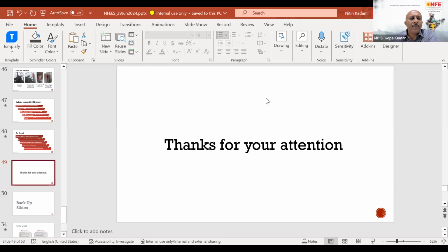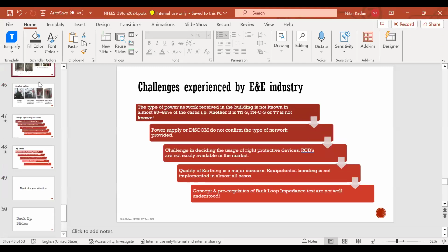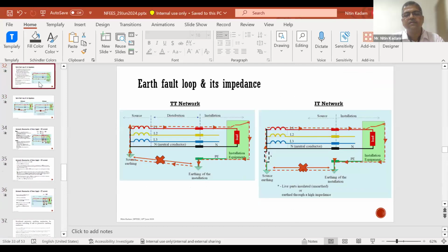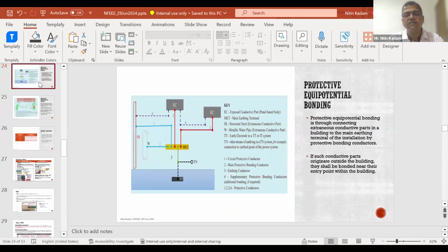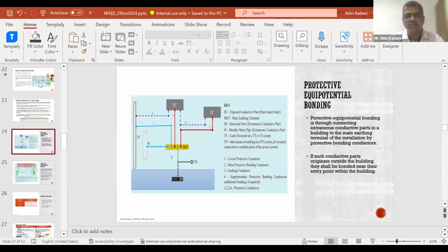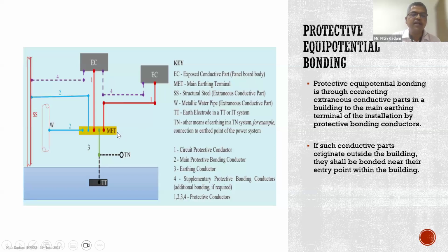If you remember the slide, maybe I can share my screen again. Can you see my slide? Yes, please. So I'll just go back. Maybe I can take this automatic disconnection, the protective equipotential bonding here. I was explaining on the slides that there is a MET terminal, the main earthing terminal of the building, and in case of a TN network it is expected to go back to the source earthing and not to the local earthing given on the site. And in case of a TT network, it is expected to be connected to the local earthing.